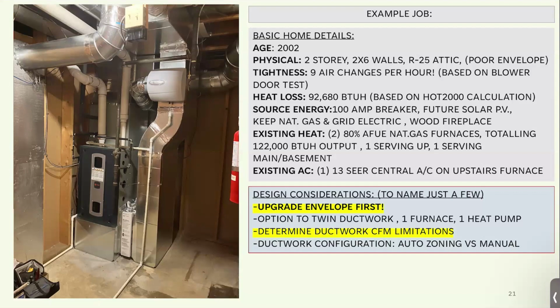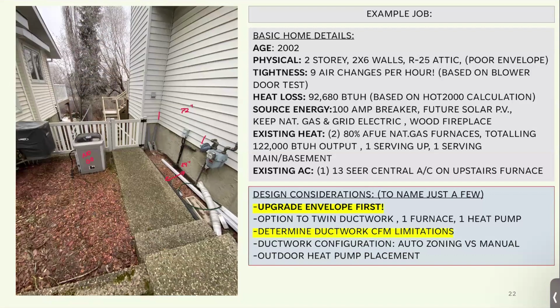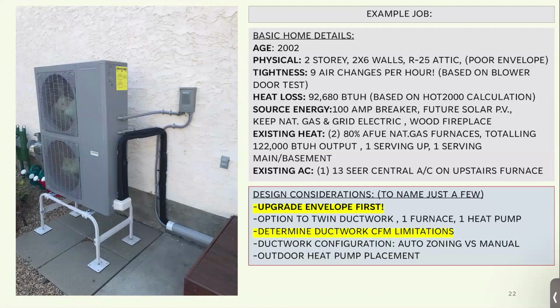It's ran great. Now, looking at the outside, it was another challenge, as the AC was run to the other side of the sidewalk, underground line sets. It's not a good thing to do a heat pump with a long line set outside. You're going to lose all that precious heat from the compressor through losses to the atmosphere. So we had to change up that situation. And so we gave them a pad and stand, moved it around the corner.